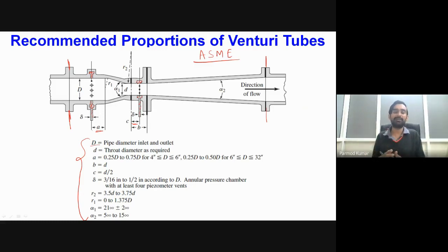Okay, so why? Because the entire circumferential periphery will be giving a good estimate of the average pressure. Okay, so this is how pressure taps are designed. And particularly if one has to design a Venturi for any specific pipe conditions or flow conditions, one can follow this particular standard for designing the Venturi.